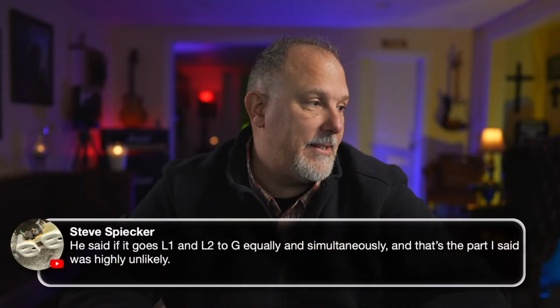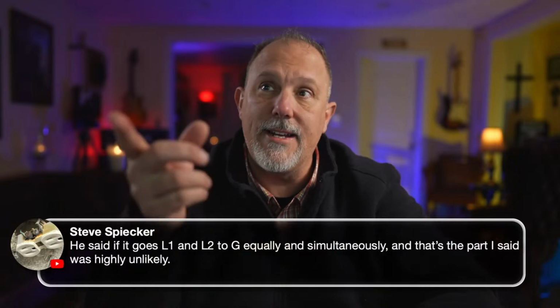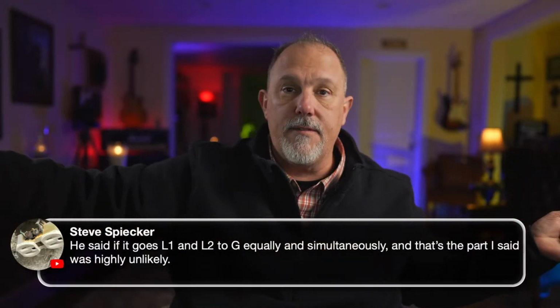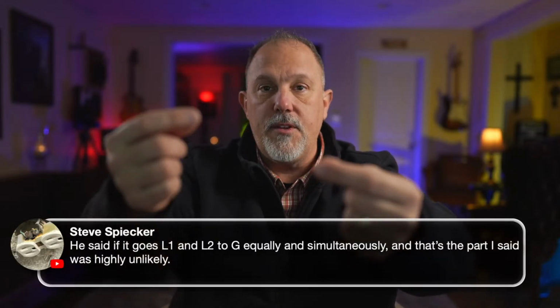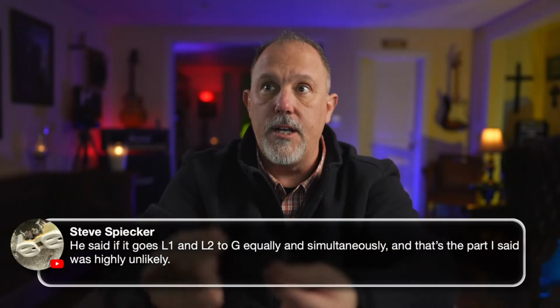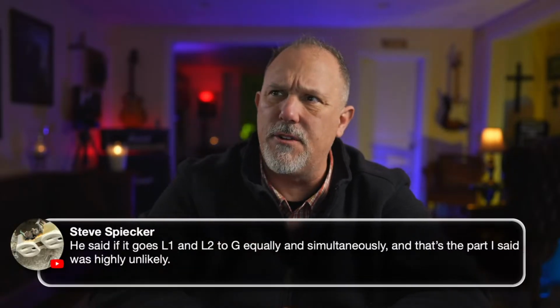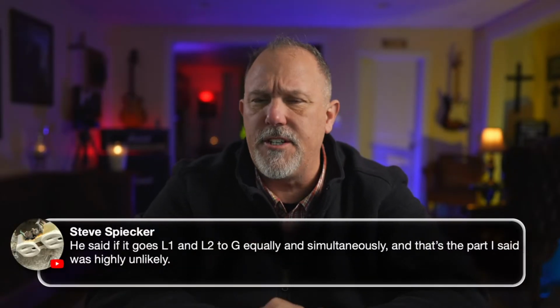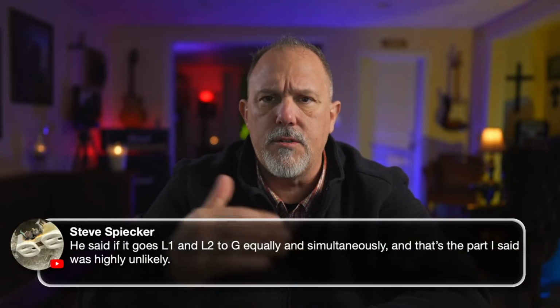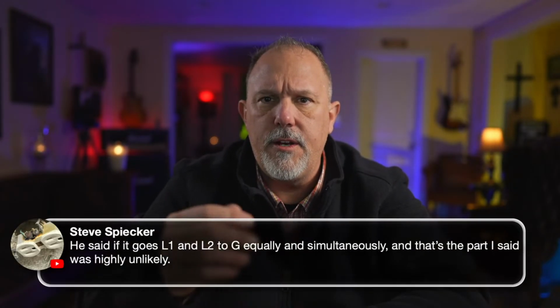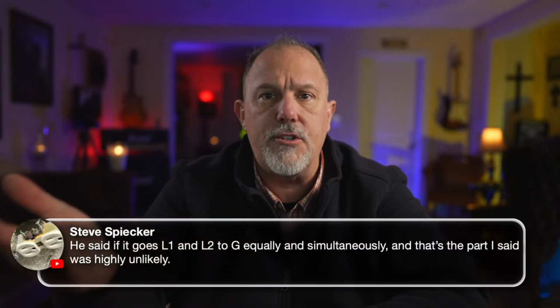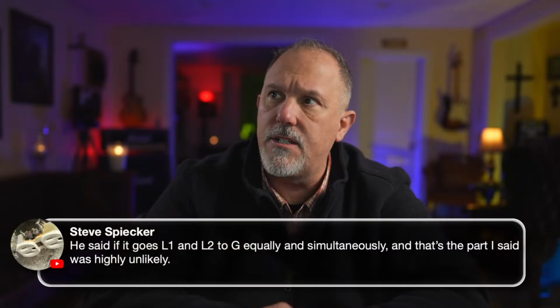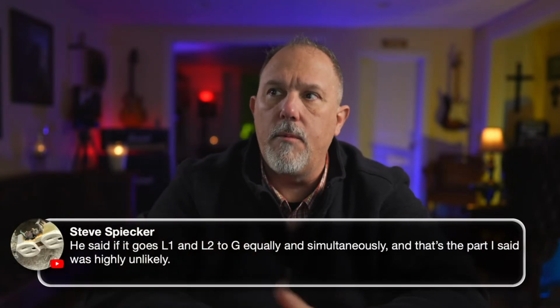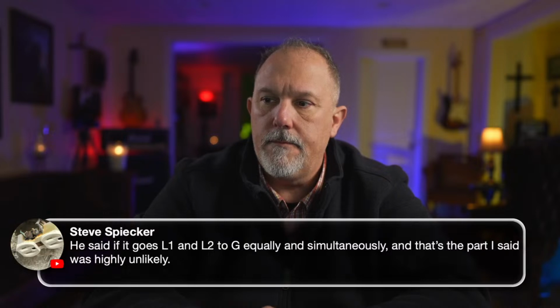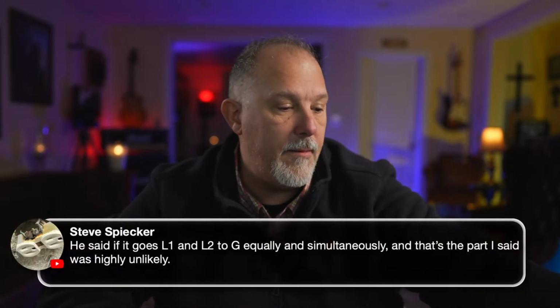I'd love to see the test. You could set this up. All you got to do is put a resistor out, take a length of run of conductor, take an impedance and put it between each of the phases to ground to pull 2 milliamps. 2 milliamps each is only 4 milliamps total. It's not going to trip a GFCI at 4 milliamps. Remember, the threshold's 4 to 6 milliamps. You need around 6 milliamps for the let go threshold anyway. So 2 milliamps each, that ain't going to happen. You need more milliamps. So that's my opinion, and I am sticking to it.